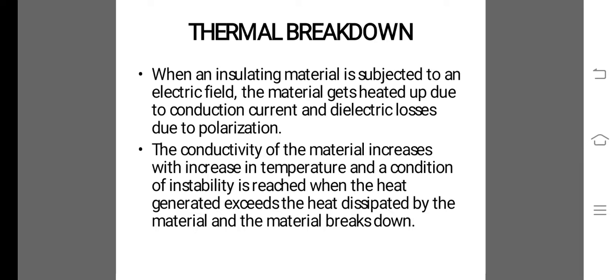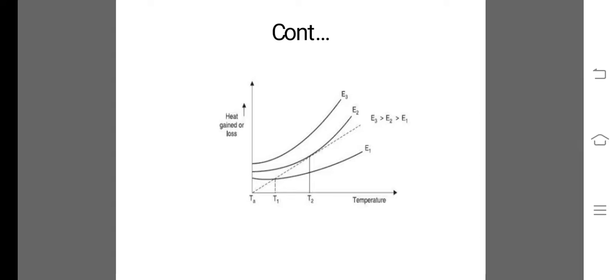Thermal breakdown: when an insulating material is subjected to an electric field, the material gets heated up due to conduction current and dielectric losses due to polarization. The conductivity of the material increases with increase in temperature, and the condition of instability is reached when the heat generated exceeds the heat dissipated by the material and the material breaks down.